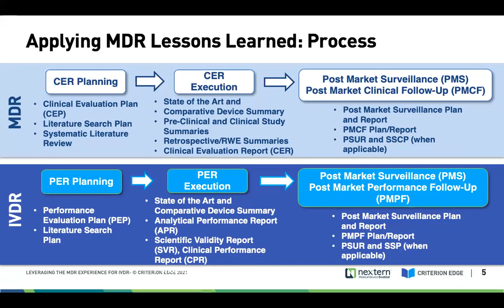And then within that, your scientific validity report and your analytical performance report directly support words that you've placed now in that intended purpose statement. So I guess my point is, I think the notified bodies and the regulators are definitely looking for explicit ties between the way in which you say this is how my product is intended to perform, and here's where it is, maybe in a panel of other diagnostic devices. This is where it plays, and make sure you're really crystal clear on, I'm saying my intended purpose is this because of how it fits in this broader clinical continuum. And then here's my analytical performance report to support these claims. And here's my SVR that supports how I've positioned it within the state of the art.